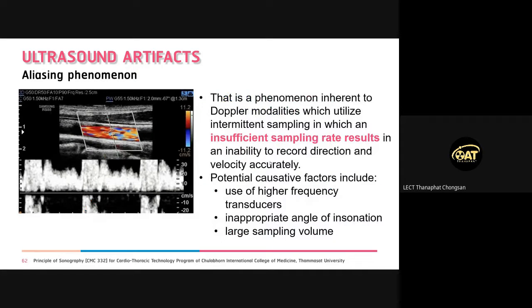Okay, next artifact is aliasing phenomenon. Everyone can see aliasing phenomenon in Doppler imaging. It is displayed as mixing between red and blue areas.